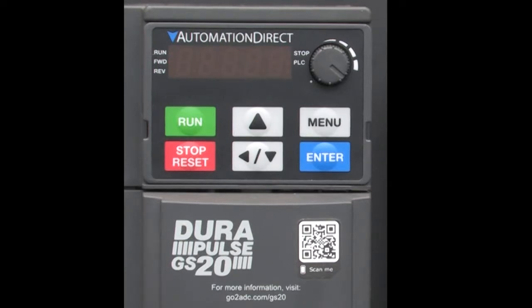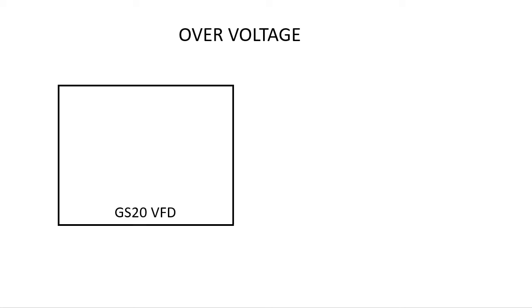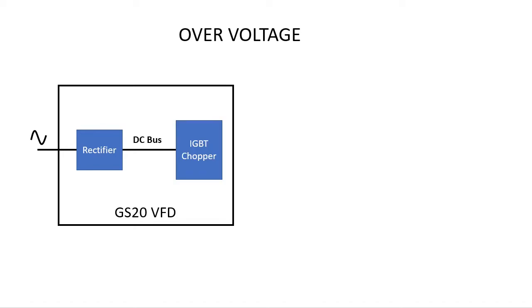Well, before we get into that, let's step back and make sure we understand what is actually happening inside the drive. In the simplest terms, a drive just takes an AC input, rectifies it to a DC voltage and then uses some large transistors called IGBTs to pulse width modulate or chop the DC voltage.